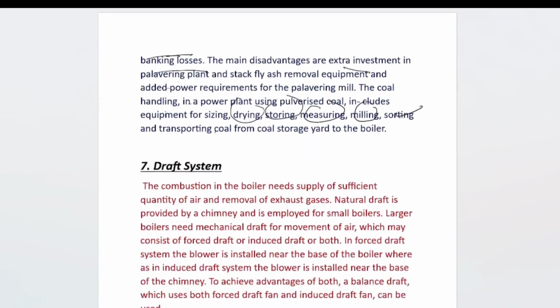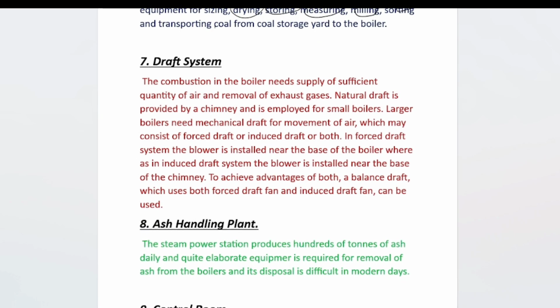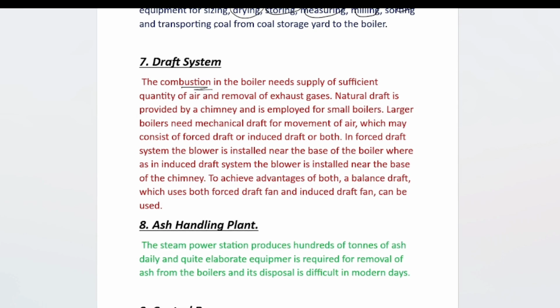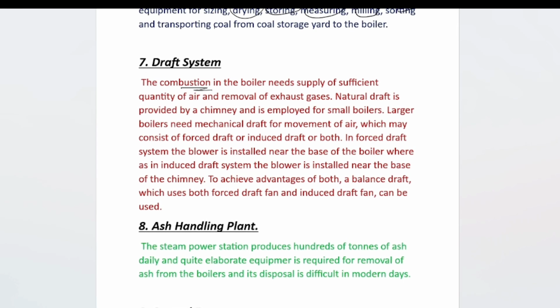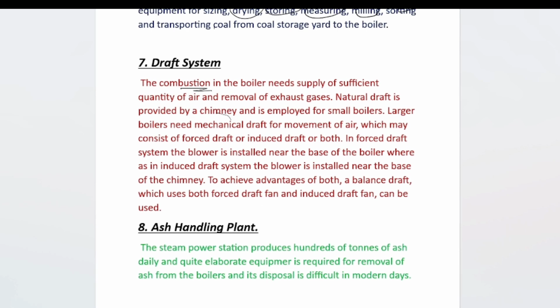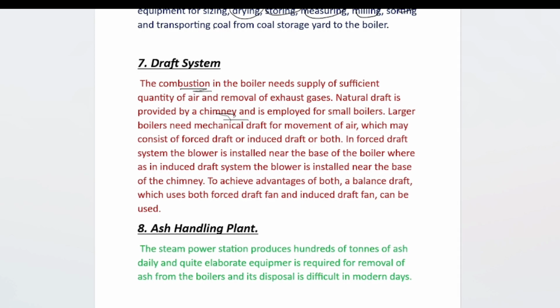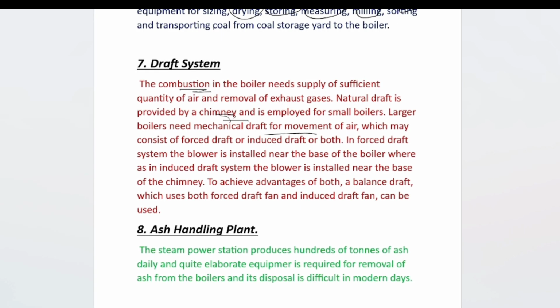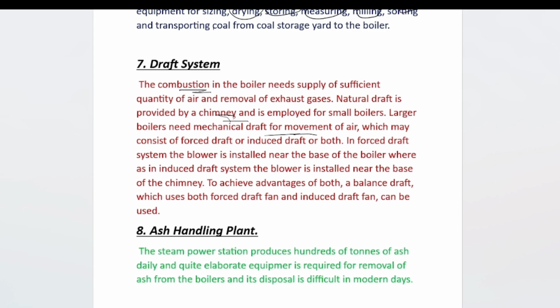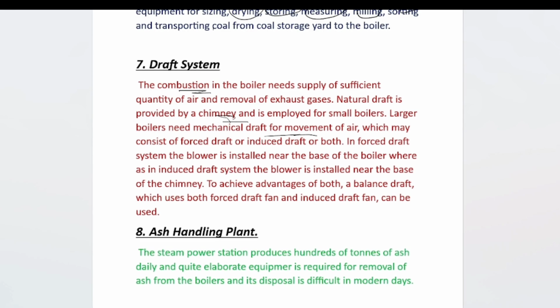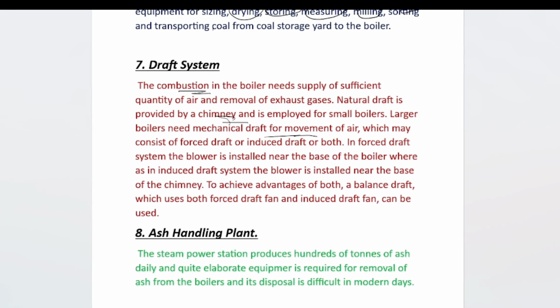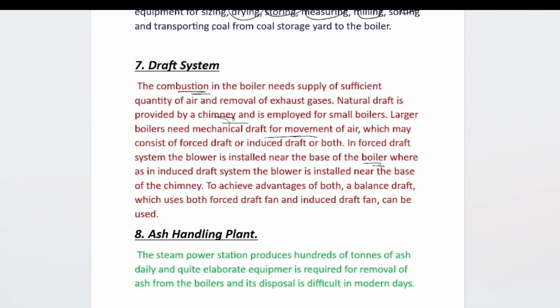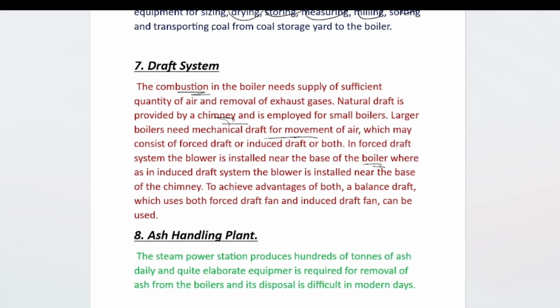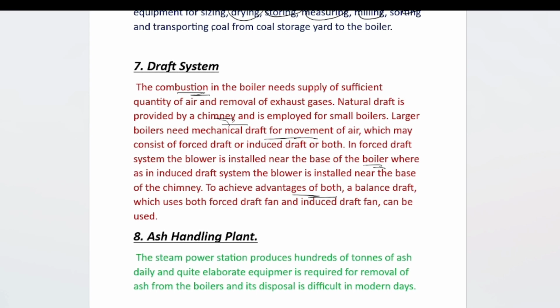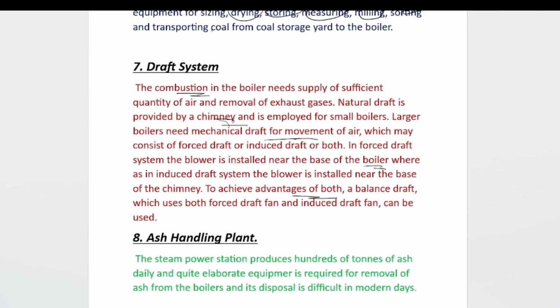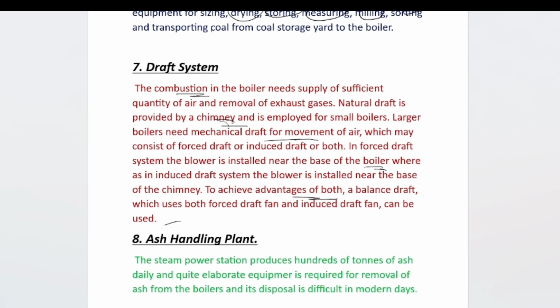Next, the seventh part is the draft system. The combustion in the boiler needs a supply of sufficient quantity of air and removal of exhaust gases. Natural draft is provided by the chimney and is employed for small boilers. Larger boilers need mechanical draft movement of air, which may consist of forced draft, induced draft, or both. In the forced draft system, the blower is installed near the base of the boiler, whereas in the induced draft system the fan is installed near the base of the chimney. To achieve the advantages of both, in balanced draft both a forced draft fan and an induced draft fan are used.